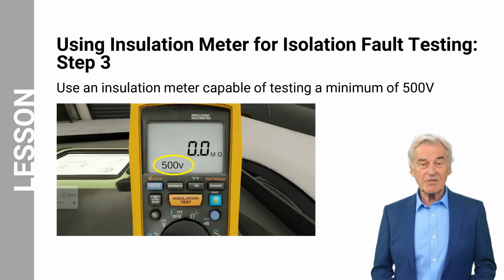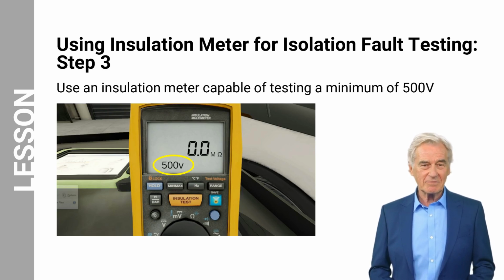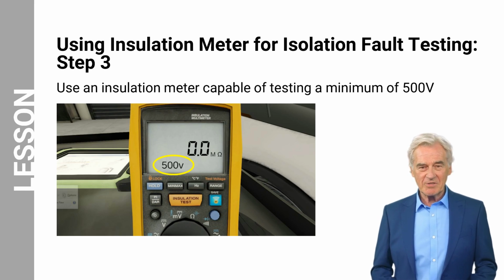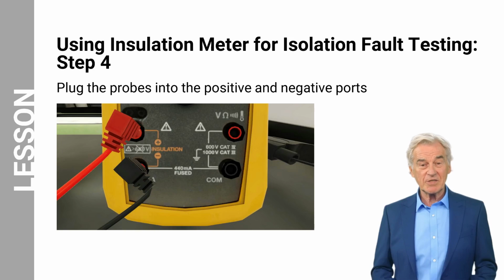Step 3. Choose an insulation meter capable of testing at a minimum of 500 volts. Before use, ensure that you read all instructions and warnings for your insulation meter. The available test ranges for this meter are 50, 100, 250, 500, and 1000 volts. Choose the range button for your meter to display 500 volts. Step 4. Plug the two probes into the correct positive and negative ports.